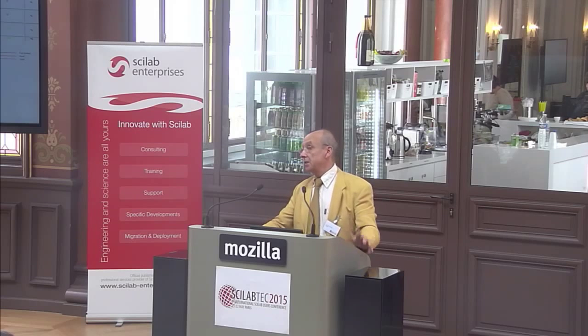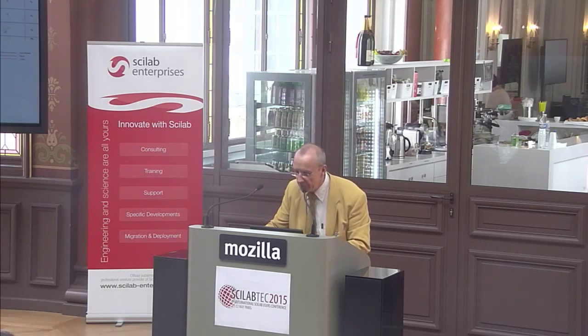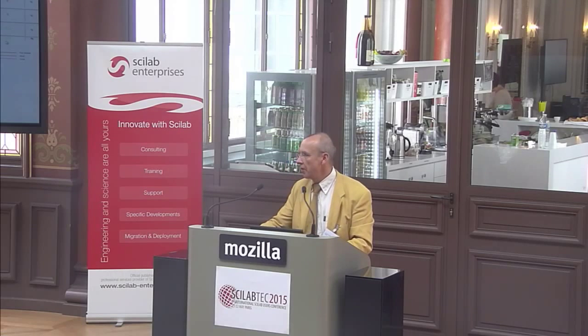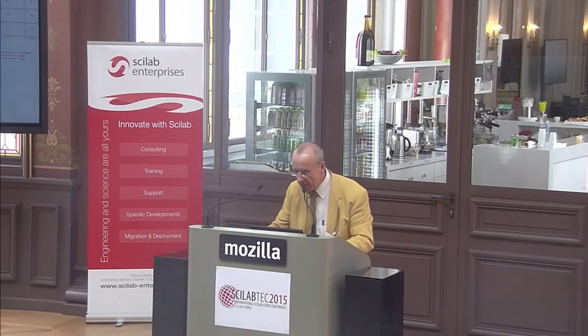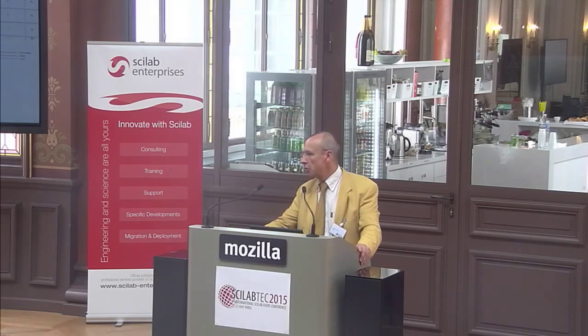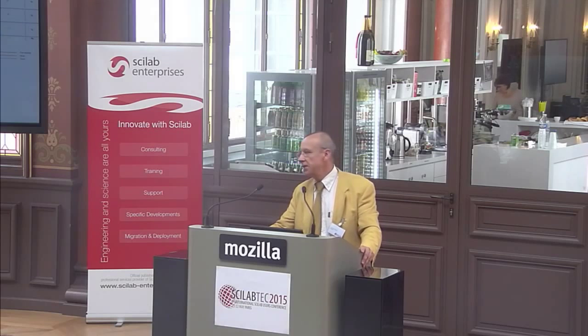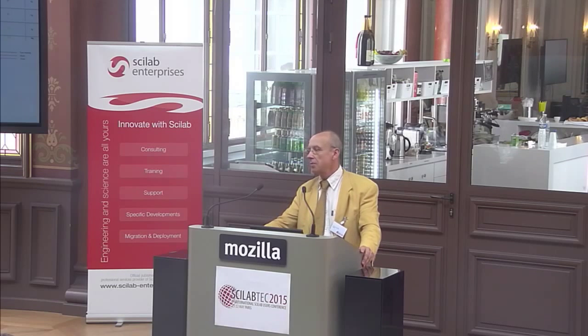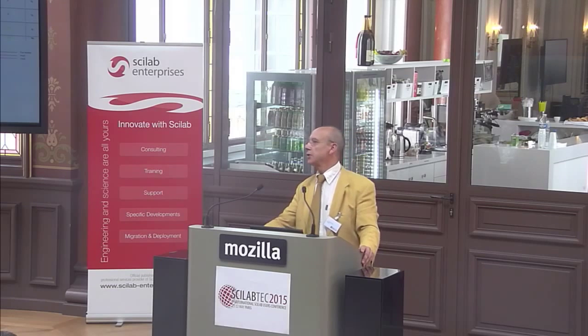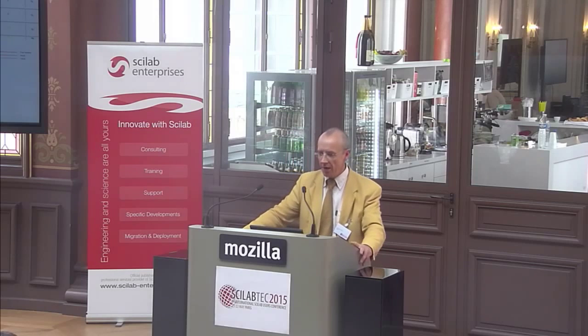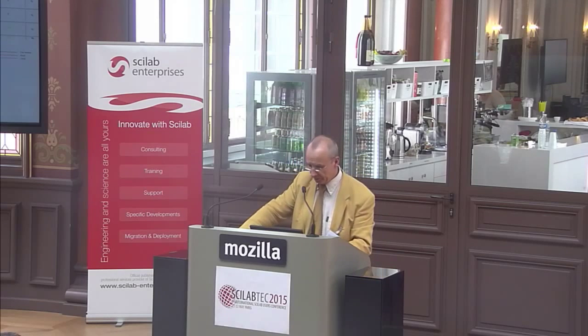As expected, you see that you have a pretty good cut: 2.9% of energy consumption, of electrical consumption, and the payback over the year is something like 284 euros. So you can ask yourself, is it worth really doing this modification? Because the payback is not so obvious considering the cost of the drive. So if somebody from Schneider is attending, I can discuss with him, or Siemens, or any company supplying this category of drive.